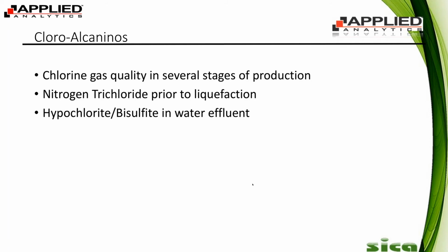And next is chlor-alkali. As you can see so far from this presentation, H2S is a very common chemical that we measure. It's our number one measured chemical. I would say that chlorine is pretty close behind it. In the chlor-alkali process, mainly measuring high percent level of chlorine is our best application. We have many applications in it, such as measuring nitrogen trichloride, or NCl3, which is a contaminant in the process, and it has a very low explosive limit, so it has to be monitored basically throughout the process to ensure it doesn't get above it.